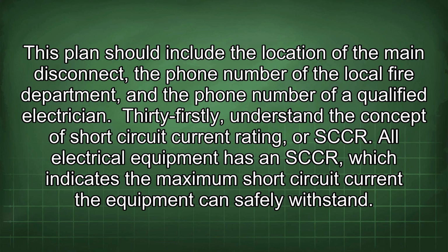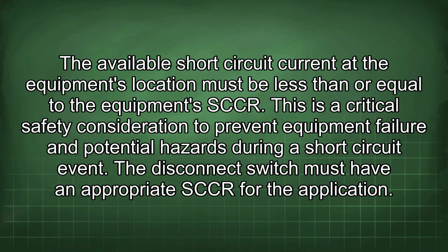31st, understand the concept of short circuit current rating, or SCCR. All electrical equipment has an SCCR, which indicates the maximum short circuit current the equipment can safely withstand. The available short circuit current at the equipment's location must be less than or equal to the equipment's SCCR. This is a critical safety consideration to prevent equipment failure and potential hazards during a short circuit event. The disconnect switch must have an appropriate SCCR for the application.